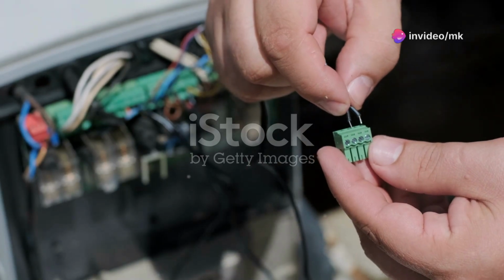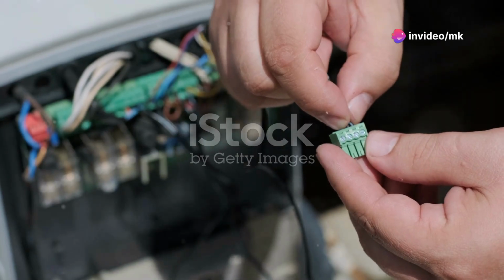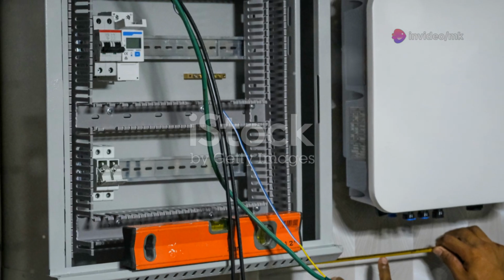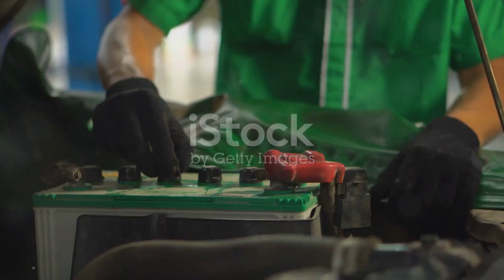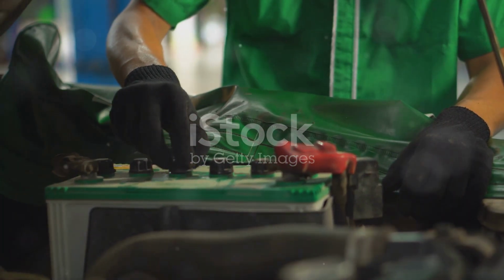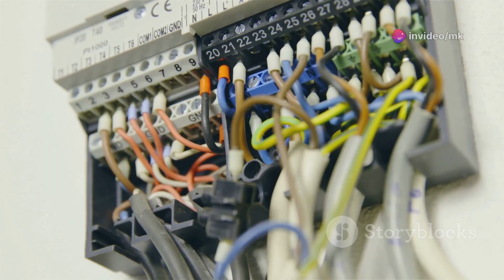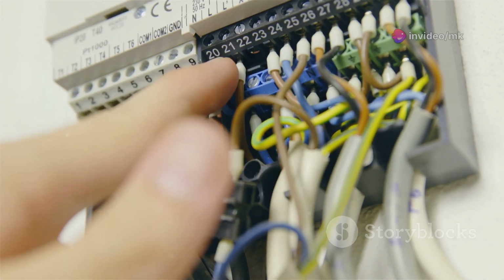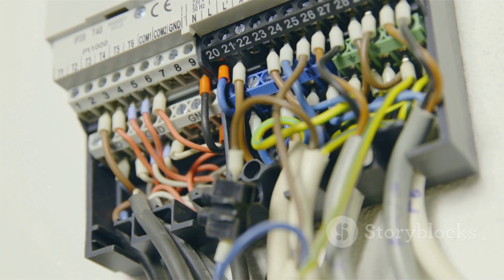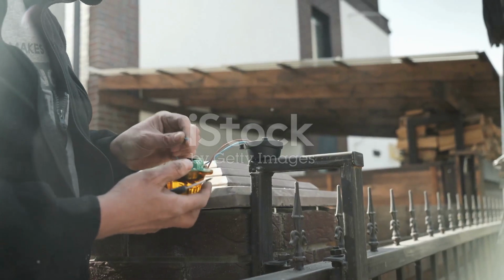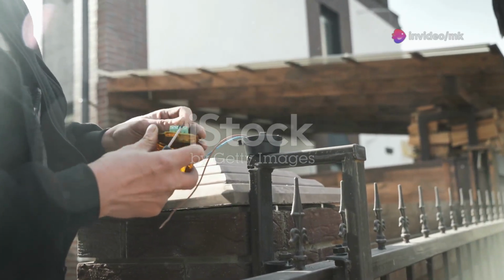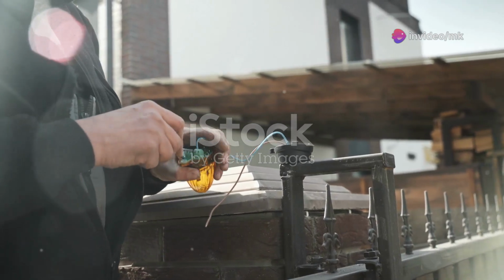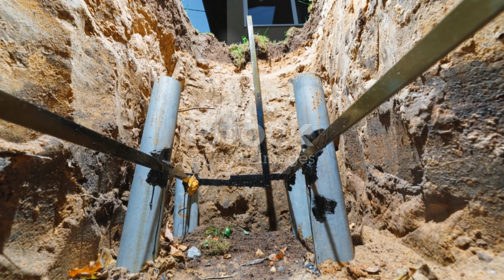Second, the DC combiner box and inverter chassis, the metal enclosures of these need grounding lugs connected to that same grounding wire. The inverter always has a specific grounding terminal, so use it. Third, the battery bank rack or enclosure, if it's metal, ground it and connect it to the main grounding wire. Fourth, AC components like the disconnect, ATS, and main panel, all metal enclosures on the AC side must be bonded together and connected to the ground bus bar inside your main electrical panel. And fifth, the earth itself. All these grounding wires must ultimately connect solidly and securely to your main earth electrode or ground rod, buried deep outside your house. This is the final, crucial link that sends any stray electricity safely into the ground.